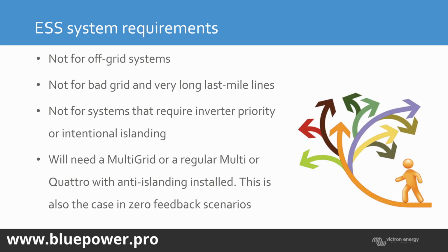So ESS system requirements: it's not good for any bad grids or off-grid systems due to the requirement of being connected to the grid for an ESS system. If you want to run an off-grid system, it's better to do dedicated no AC, or just don't run any assistants. And as soon as the grid connects, or there's a generator available, they will charge your battery, feed your loads, and you can control that by other means with contactors on the inverter if need be. But yeah, ESS systems are made for grid-connected hybrid solutions.